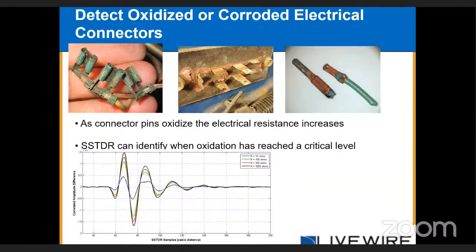If you have a system that is built in and testing continually, you can be quite sensitive to these types of small changes. However, if you wanted to walk up with a device later, like a handheld, you might not recognize those very small faults and be able to find them. So the best way to locate very small faults or very small intermittent faults is to build the system in, to actually embed it into the system itself.